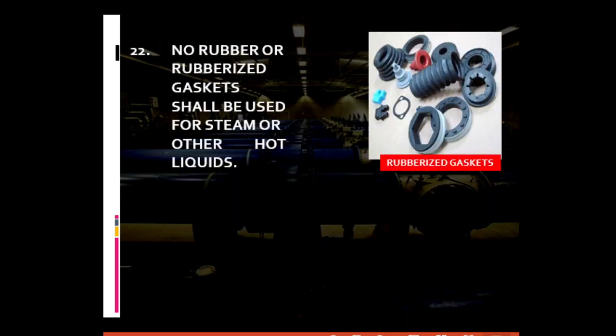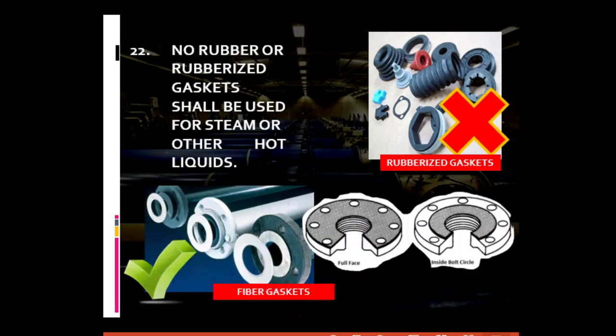For general piping requirement number twenty-two: no rubber or rubberized gaskets should be used for steam or other hot liquids. Flange connections make use of gaskets to allow for easier separation or disassembly between flange pieces. Making use of rubberized gaskets is not possible when the substance to be conveyed is a high temperature fluid, as it can cause possible damage to the gasket. Instead, make use of fiber gaskets — made from a special kind of compressed fiber that can handle the high temperature characteristic of steam or other hot fluids.